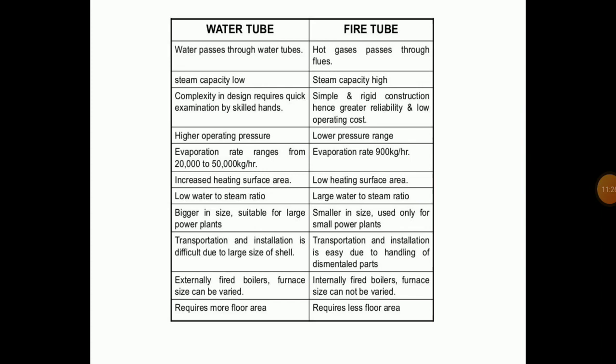In water tube boilers, water passes through the water tubes while the steam storage capacity of these boilers is low. The complexity of design requires examination by skilled hands and high operating pressure is generated. The evaporation rate ranges from 20,000 to 50,000 kg per hour. The low water-to-steam ratio makes them larger in size and suitable for large power plants, though transportation and installation is difficult due to the large size of the shell.